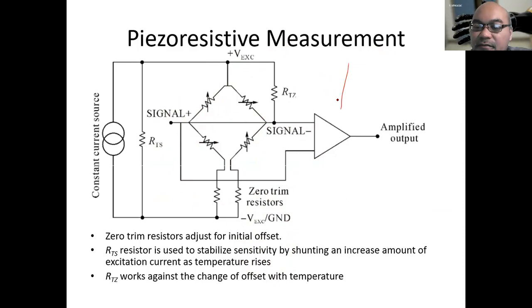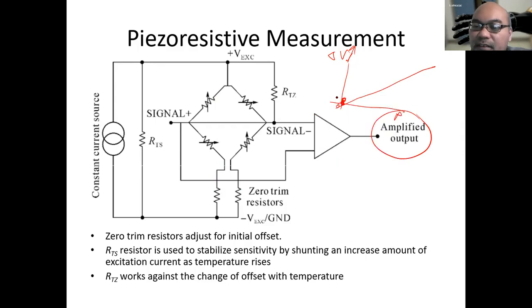Remember offset: when the stimuli is zero, for example pressure on one axis and delta V, the amplified output, on the other, what we want is that delta V is also zero, then it increases linearly with increasing pressure. However, without this zero trim resistor, we might end up with an offset, where even with no pressure difference there is already a delta V. This is what we call offset.